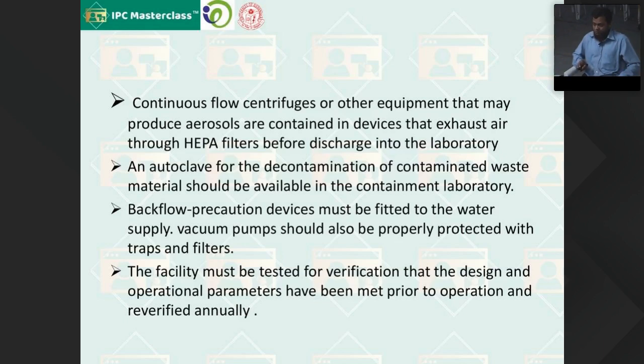An autoclave should be there for the decontamination of contaminated waste. If you have seen in BSL 1 and 2, the autoclave is not inside the lab, but in BSL3, it has to be inside the lab, with backflow precaution devices fitted, so that there is no backflow, and the vacuum pumps should be properly protected with traps and filters. And the facility must be used for the verification of design and operational parameters for the biosafety cabinet.